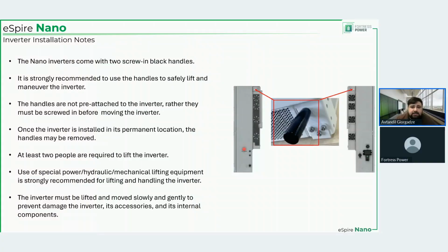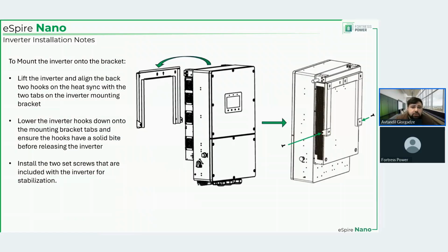Now, next, to mount the inverter, once the bracket is secured, you lift the inverter, and the bracket has a lip over which the inverter goes. You hang the inverter on it, and then there are 2 screws that you install in the bottom of the bracket to stabilize the installation. Otherwise, you can touch or grab the inverter and pull it towards yourself, and it will rotate around that lip which supports it. So to prevent that, please use those 2 screws that are included.